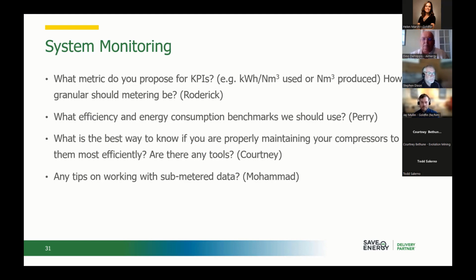We use some benchmarks as rules of thumb for things to look at or aim for. One is that kilowatt per 100 CFM, trying to get that under, say, 20 kilowatts per 100 CFM, or if it's above that, there may be good opportunities to improve the efficiency of how you're generating compressed air. For leaks, we suggest aiming for less than a 10% leakage rate overall. For pressure drop, from the outlet of the compressor room to the end of your system, try to get that as little as possible, maybe even just a couple of PSI. If it's higher than that, there may be opportunities to address pressure drop through the system.